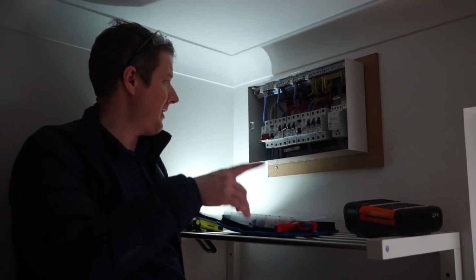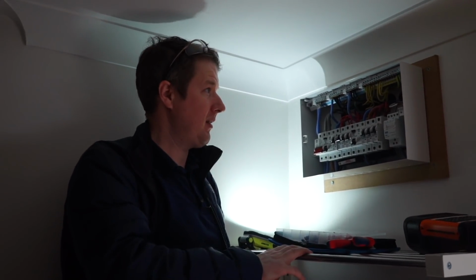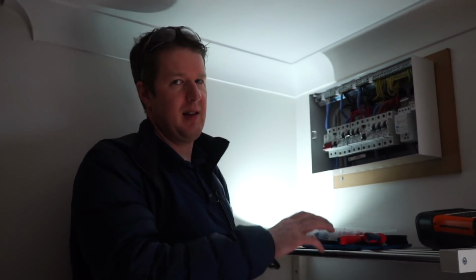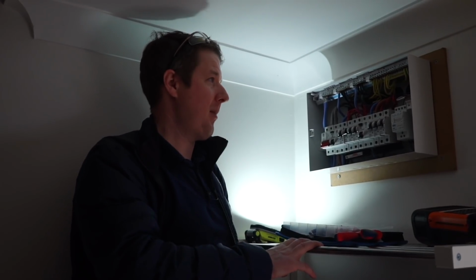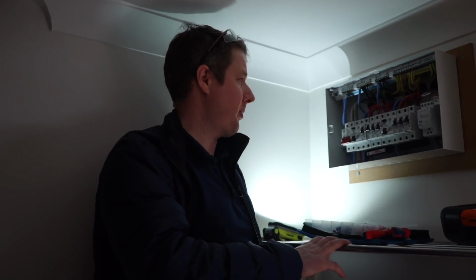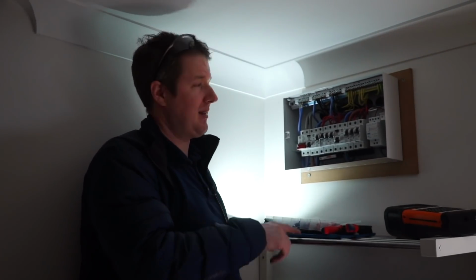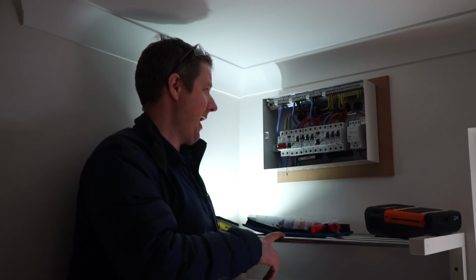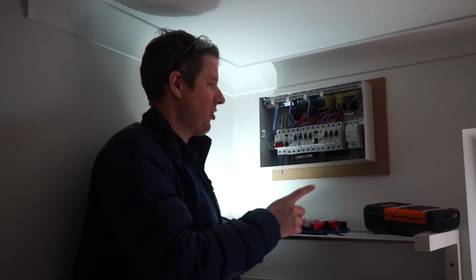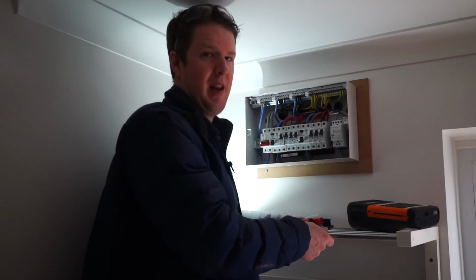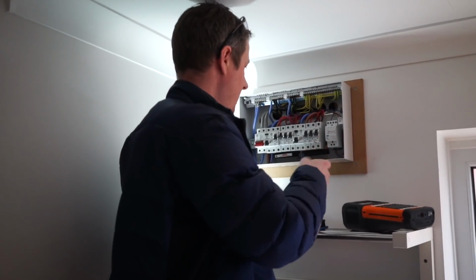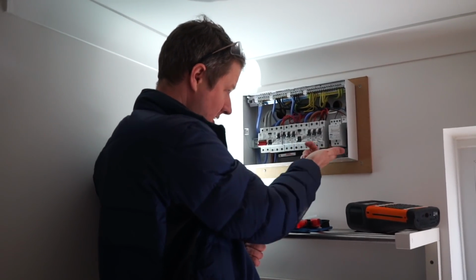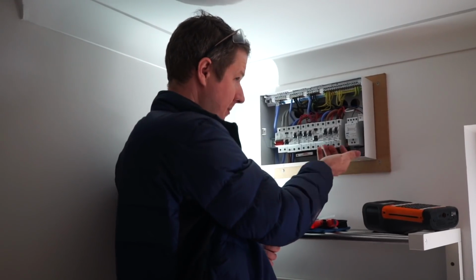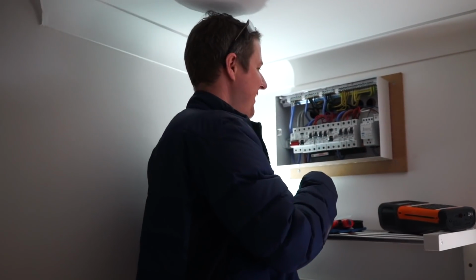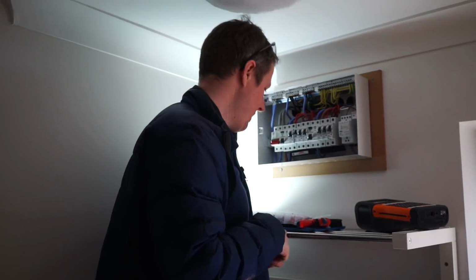So I'm going to just do a Ze test on this board just to make sure that everything's as it should be. That's an external earth fault loop impedance test. It's basically just to check that the supply cable's okay and that the main earth coming in is acceptable. Especially if we're going to change the board later, it makes sense to know about any issues that there might be now so that we can prepare for them later on. But I'm sure it's fine as it's a fairly modern house. It's from the 1980s. So I'll do Ze. I'll check with my mirror underneath here just to make sure that the bus bar teeth are all in properly, and then we'll liven it up and hopefully it all works.